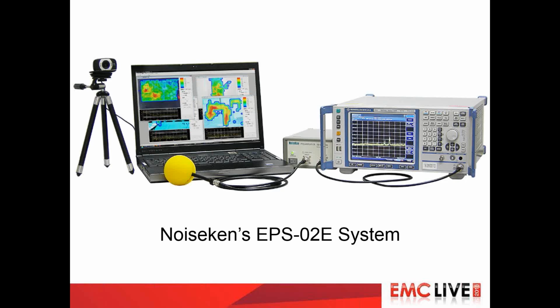NoiseKen has a space magnetic field visualization system, as they call it, the EPS-02E. It's a magnetic field sensor system that will work from 10 hertz to 400 kilohertz. It measures in 3 orthogonal axes, X, Y, Z, simultaneously, with a rated magnetic flux density of 2 Tesla. It is capable of sensitivities down to 2 microteslas, and can measure exposures, percentage magnetic field flux densities in Tesla.